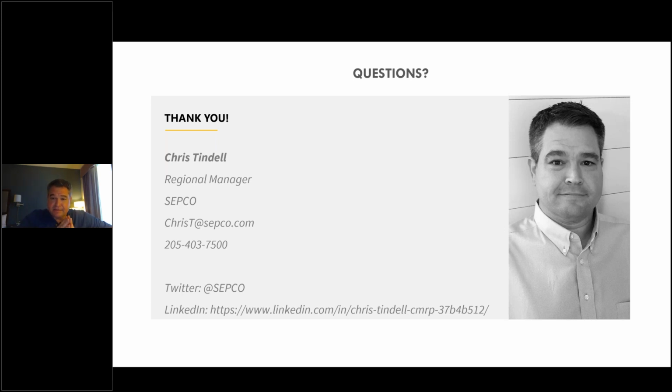But I would argue that there is a tremendous amount of information that can point us in a direction to make decisions about our rebuild process, to track the useful life of that mechanical seal, and to see if there's something wrong with the seal through the rebuild process, or something more functionally wrong with a location. And ultimately, tracking failure reports and looking at the failure mechanisms will help us understand how to address the people aspect of things. Training is a critical part of that, and there's a limited amount of training dollars. It helps us focus those dollars and resources in areas that get the most bang for the buck, the most impact.